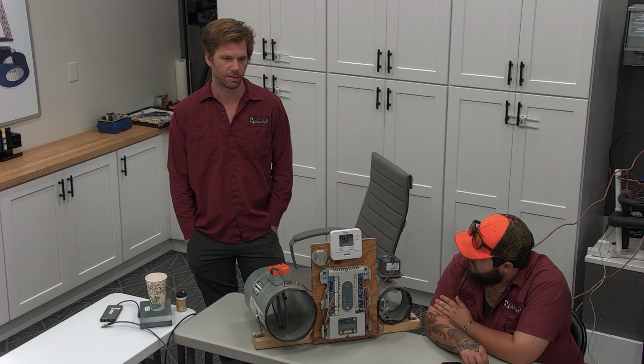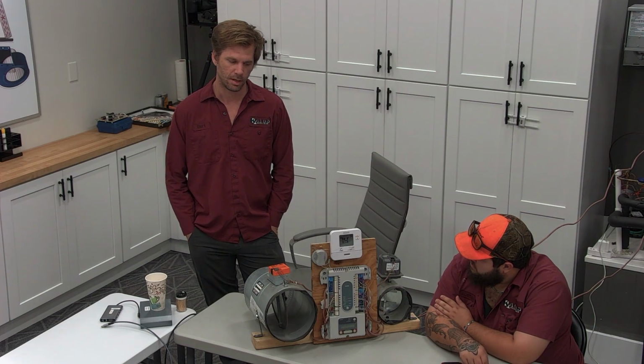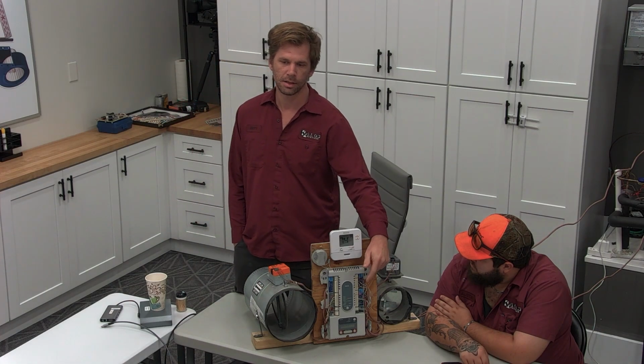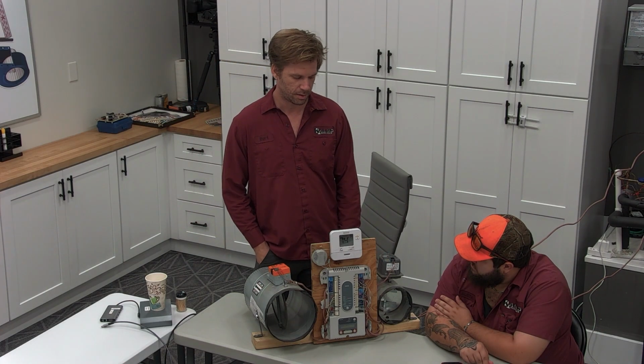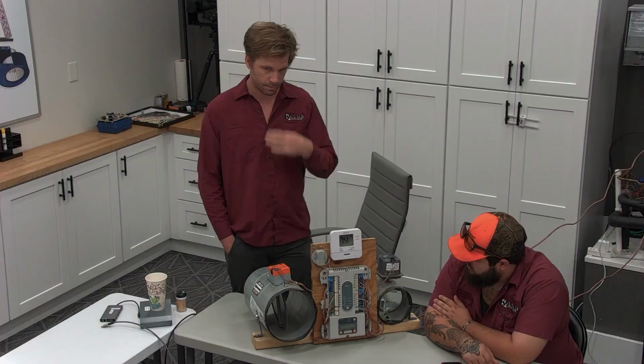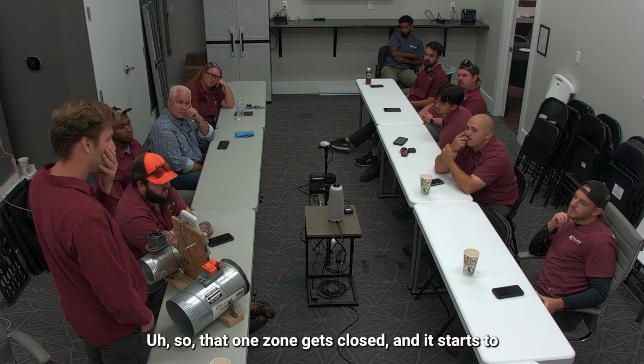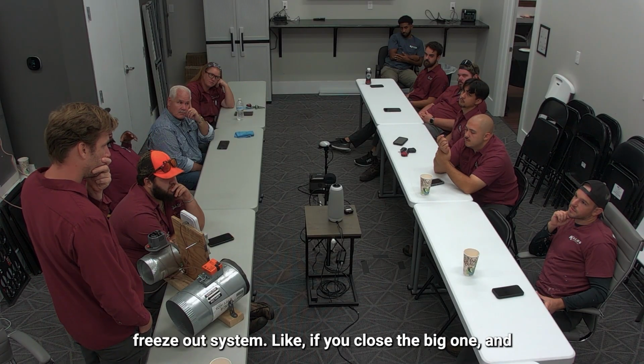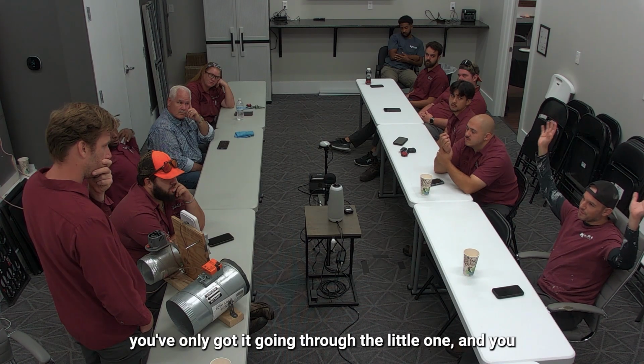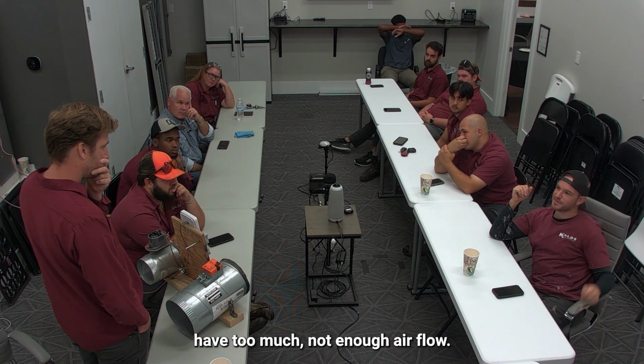So in heat, if it goes over 155, or in cool, if it goes below 45. And you can change it on something like this. Anybody know why they would need that on a damper system? So that one zone gets closed and it starts to freeze out the system. Like if you close the big one and you've only got it going through the little one, you have not enough airflow.